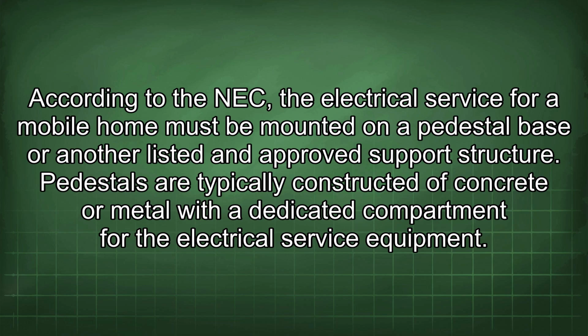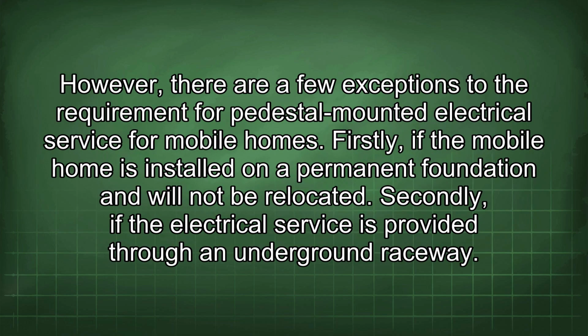Pedestals are typically constructed of concrete or metal with a dedicated compartment for the electrical service equipment. However, there are a few exceptions to the requirement for pedestal-mounted electrical service for mobile homes. Firstly, if the mobile home is installed on a permanent foundation and will not be relocated. Secondly, if the electrical service is provided through an underground raceway.